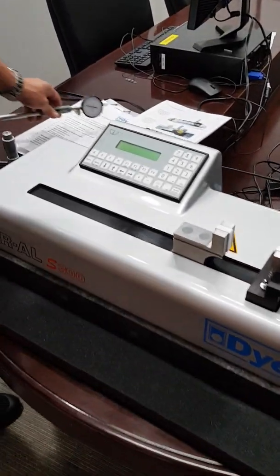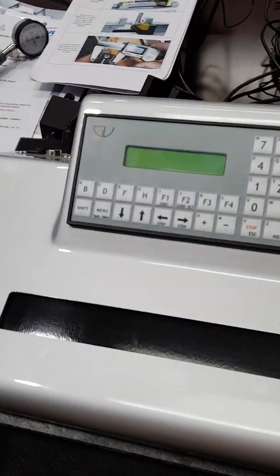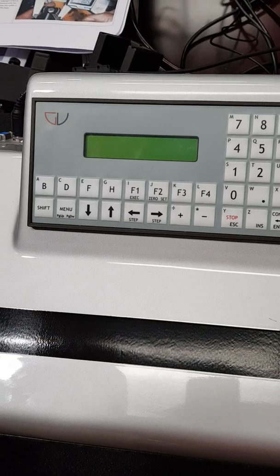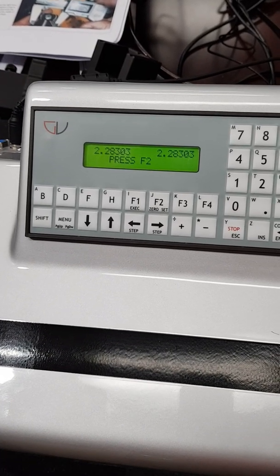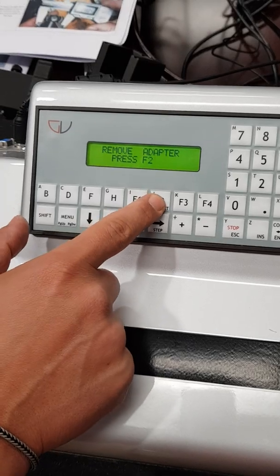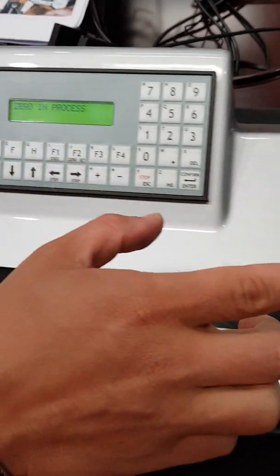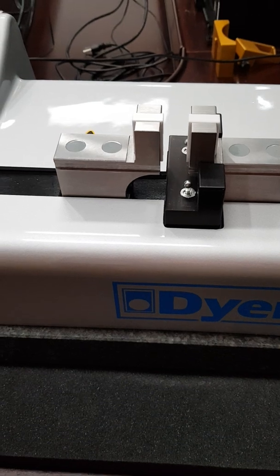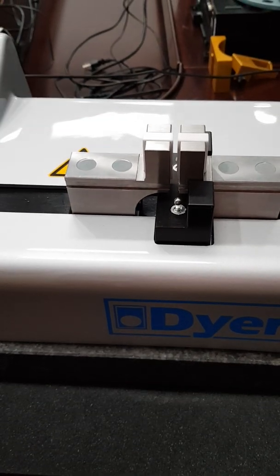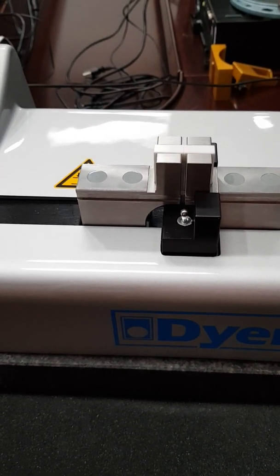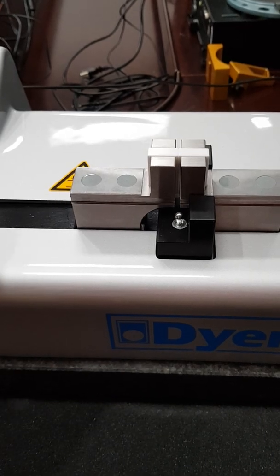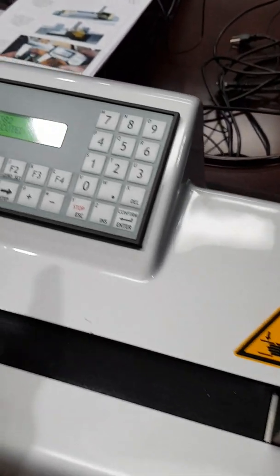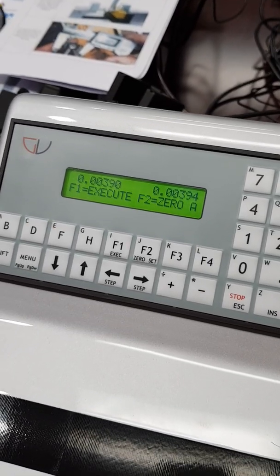Okay, let's see how this dial setting device works. The setting device for manual instruments. Turn it on. We have to press twice the zero for zeroing. Make sure no adapters are on the machine and the movable reference is going to look for the zero. In a few seconds, the machine is ready for internal values.